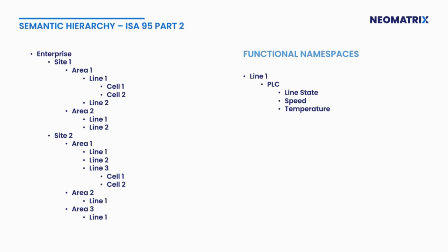Then we can add, let's say we're going to add an MES application, right? So here, this is where the power of the unified namespace starts to act. The MES platform can subscribe to information from the PLC data and then go through its algorithm and calculate things like OEE and availability and performance, and then publish that information back to the broker that could then be consumed by other applications, right?